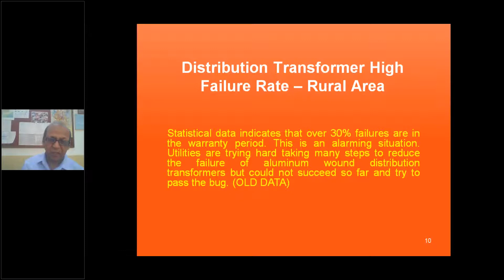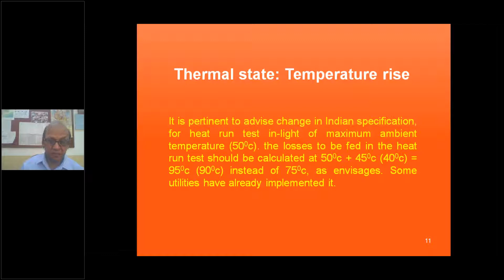We made the temperature rise, let us say winding temperature 45 degrees centigrade, that is the limit. With 50 degrees atmospheric temperature, it becomes 95 degrees, or for a smaller transformer 90 degrees centigrade. Whereas our performance temperature as per the IS is 75 degrees centigrade. Therefore, the cooling is provided corresponding to 75 degrees centigrade, whereas the temperature reaches a level of 95. So this is 20 degrees or 15 degrees extra temperature. It means it is causing faster deterioration of the insulation.